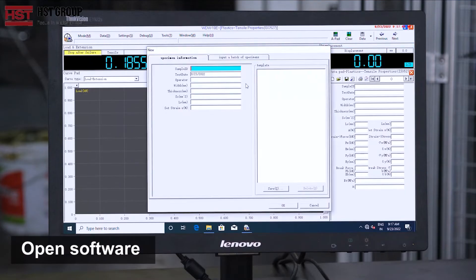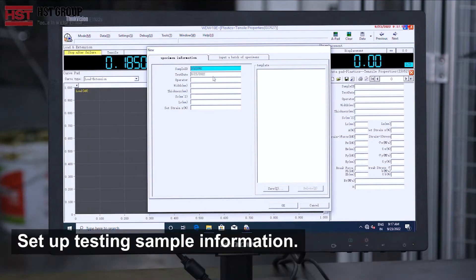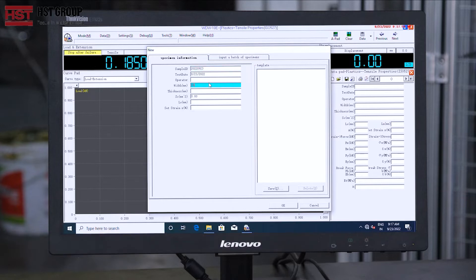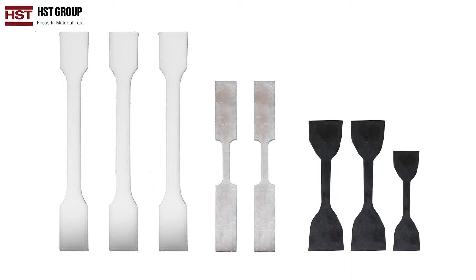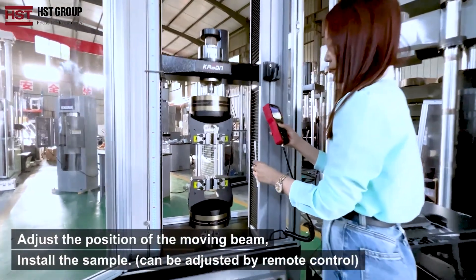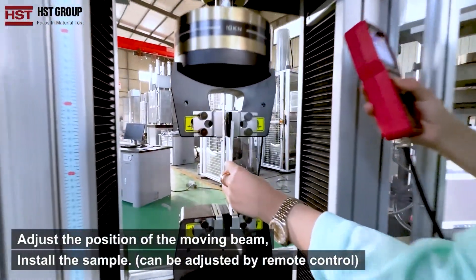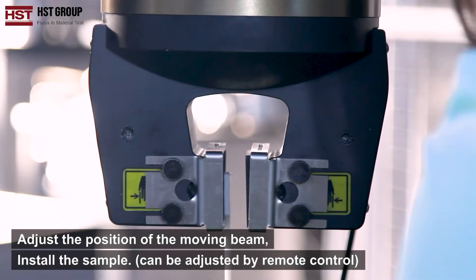Open the software and set up the testing sample information. Adjust the position of the moving beam and install the sample. The position can be adjusted by remote control.